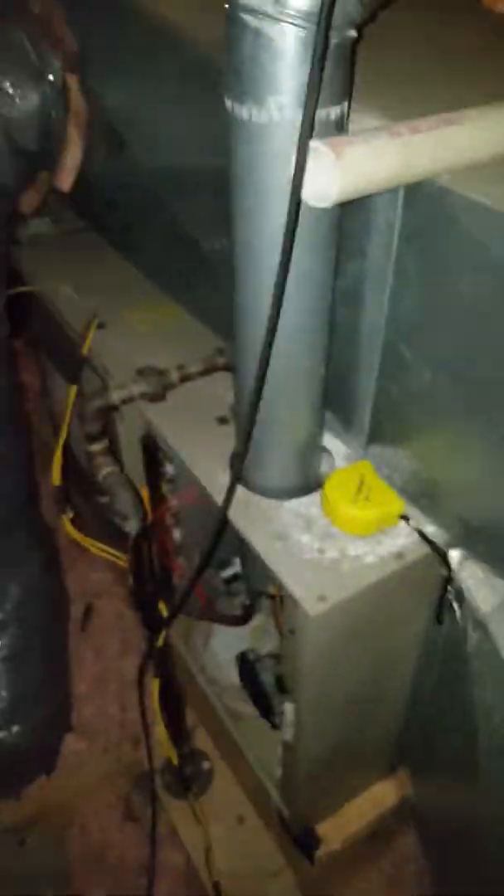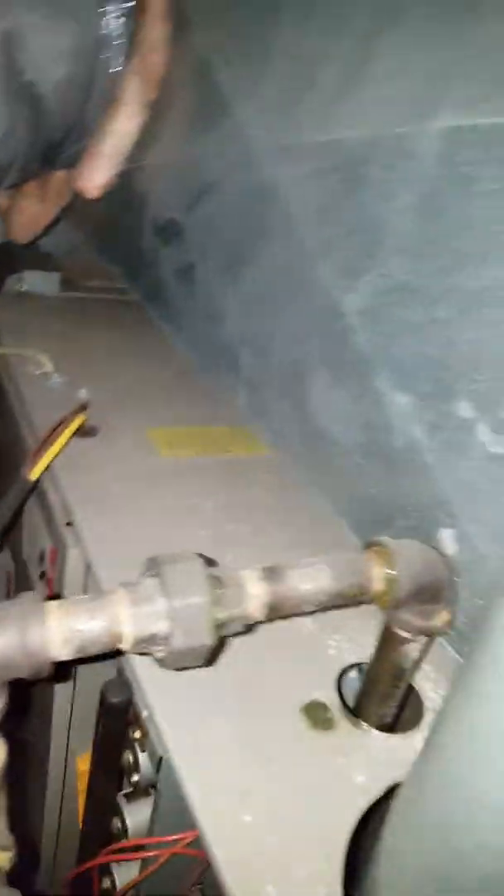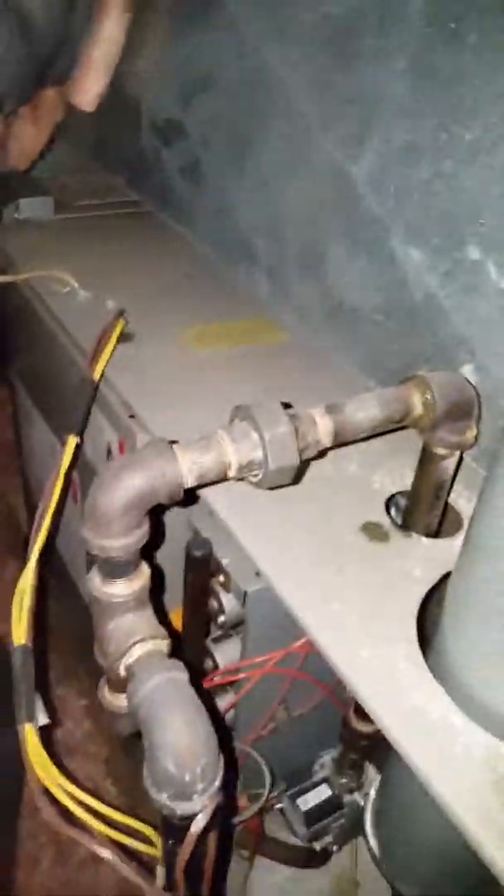So that's about it here in the attic. Got a half-inch gas line — actually three-quarter coming in with a handle valve, which is good. It reduces to half-inch and drops into the furnace with a solid half-inch line. And that is about it.